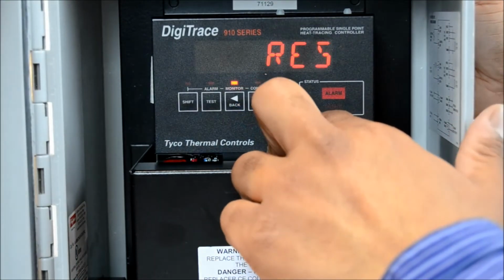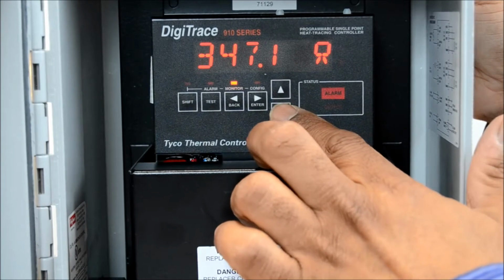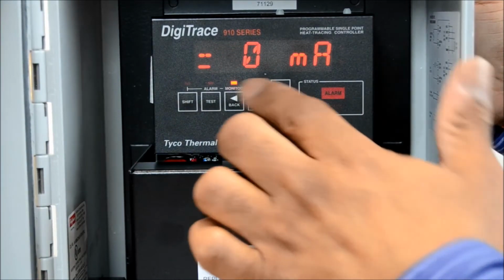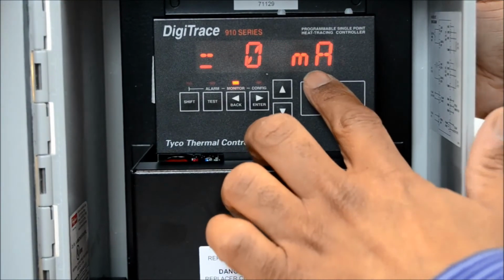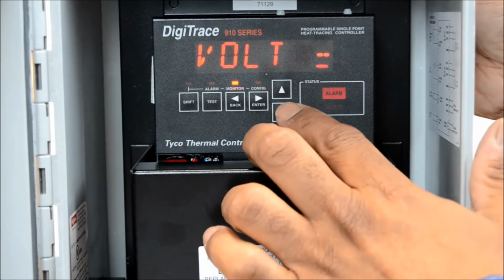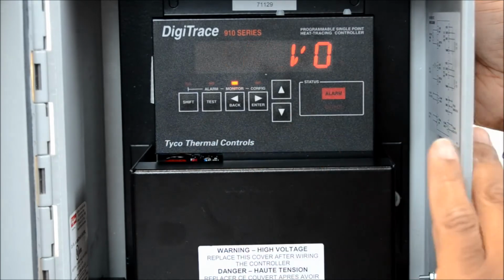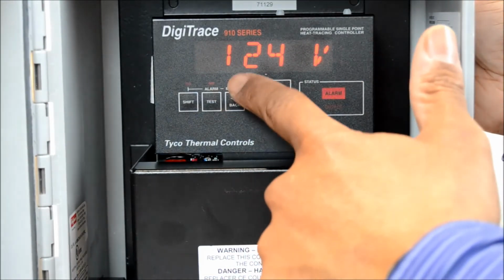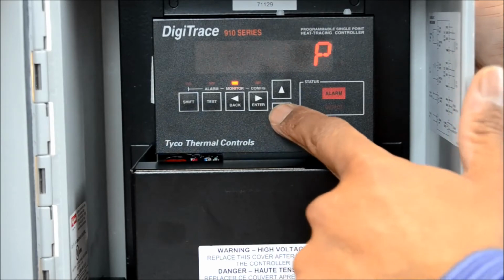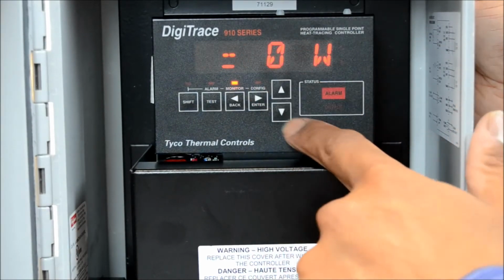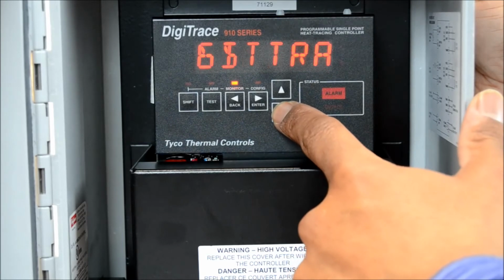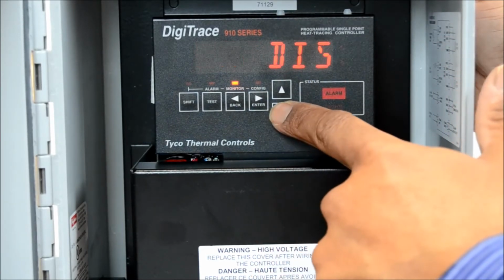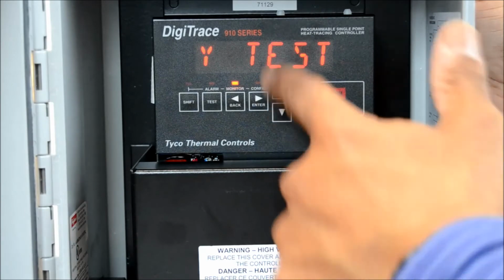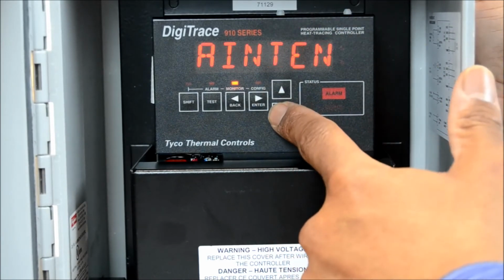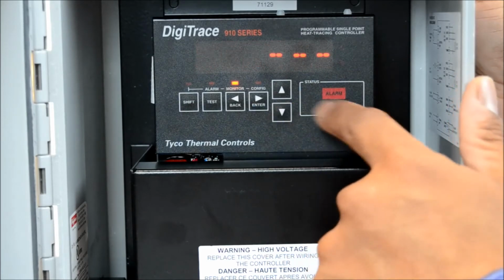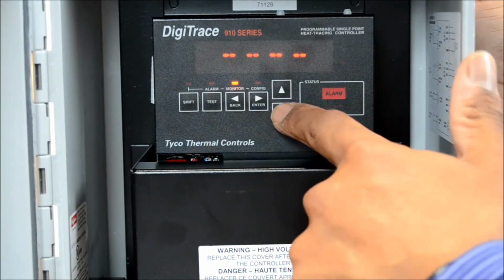You're going to go down to resistance. The next function is any ground fault, and that says 0, and that's a good sign. Voltage is next. This is set up for 120 volt right now, so you're reading 124 volts, so it can monitor that voltage. And then the power output is 0 right now because the heat trace is not on. Then you also can test the heat trace, display tests for this device here, and then any maintenance data. And then that's the end of the menu.